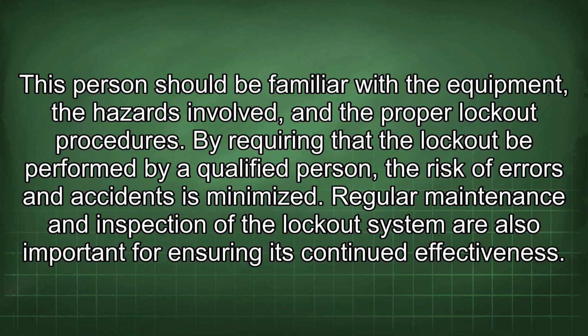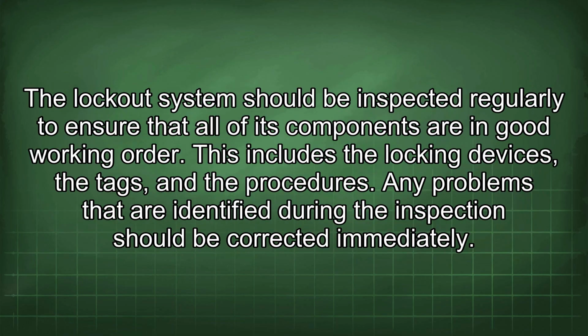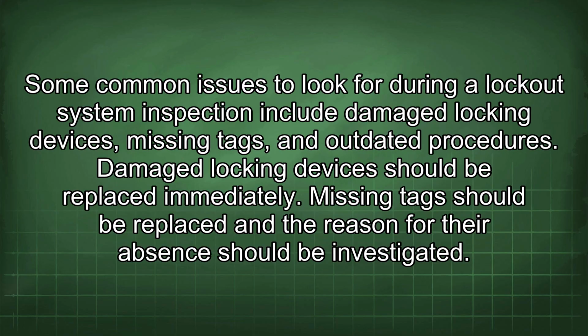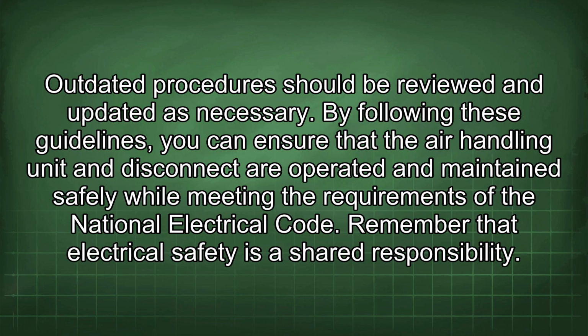Regular maintenance and inspection of the lockout system are also important for ensuring its continued effectiveness. The lockout system should be inspected regularly to ensure that all of its components are in good working order. This includes the locking devices, the tags, and the procedures. Any problems that are identified during the inspection should be corrected immediately. Some common issues to look for during a lockout system inspection include damaged locking devices, missing tags, and outdated procedures. Damaged locking devices should be replaced immediately. Missing tags should be replaced and the reason for their absence should be investigated. Outdated procedures should be reviewed and updated as necessary.